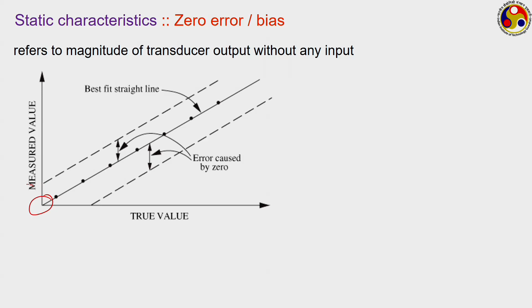That is what we refer to as zero error or zero bias. It can be on the positive side or the negative side, like in this case. So, we have to be careful about the zero bias of our instruments, and ensure that the instrument indicates zero output when there is no input. If there is any zero bias, we need to keep a note of it, because whatever final reading you get, you have to add that zero bias to get the actual value of the measurand.